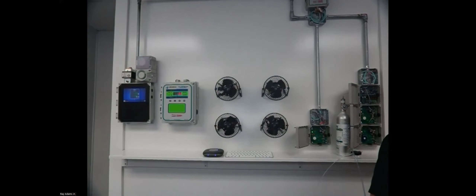It's not. Our systems have had a high alert set point at 100 parts per million since we started manufacturing our gas detection systems. You may notice some listings have a bit of difference between those numbers, but I believe you can have someone exposed over an 8-hour period at 100 ppm, and our 100 ppm timer is set at 15 minutes.